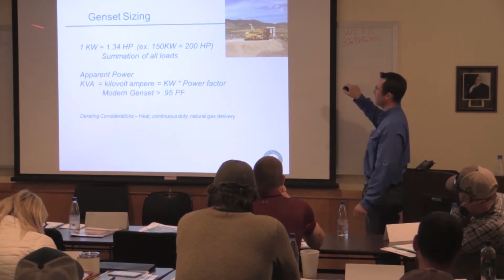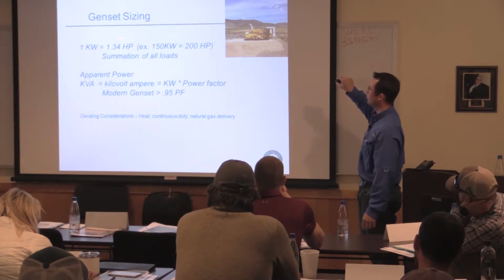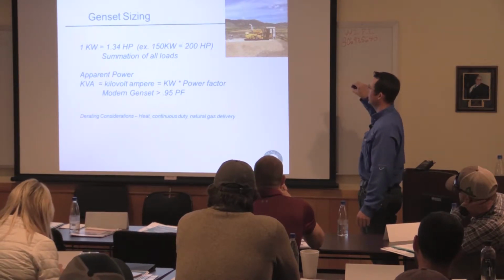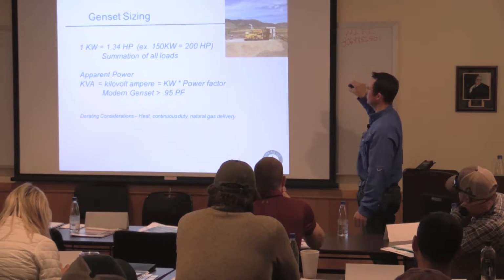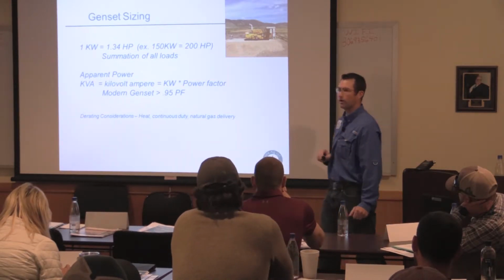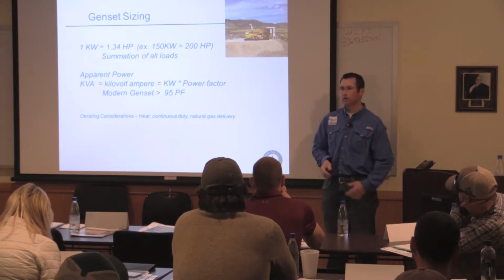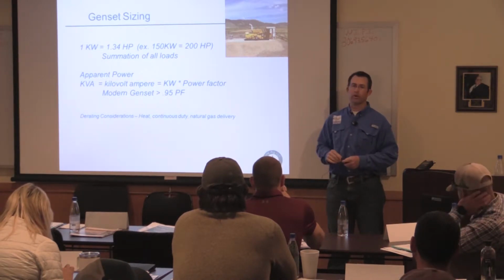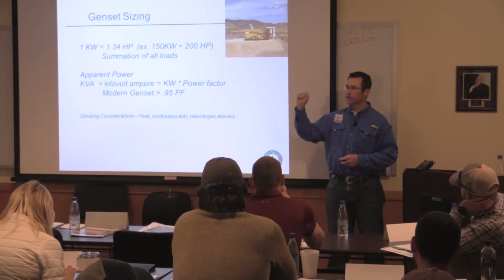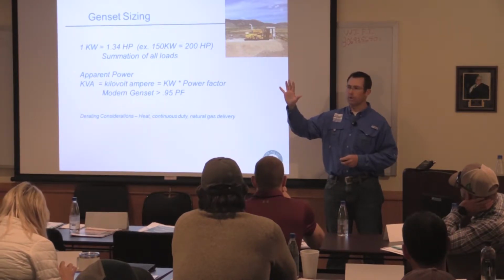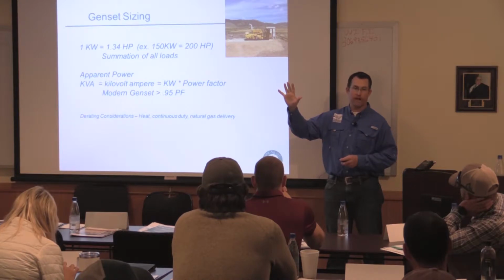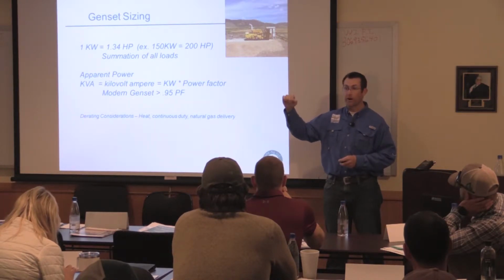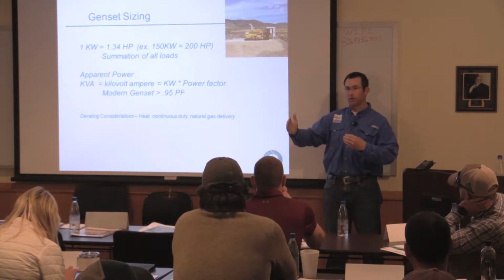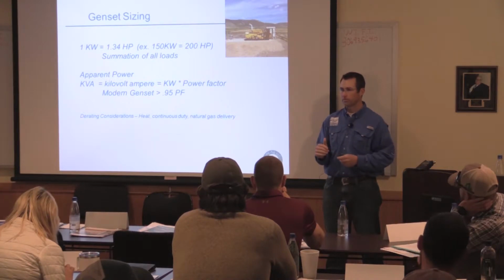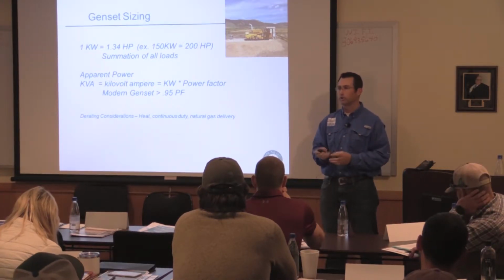The basic number that we'll look at is that 1 kilowatt equals 1.34 horsepower. So for example, if you've got a 150 kilowatt generator, you basically could be in the range of 200 horsepower for what you can operate off that. So keep it in mind, if you've got a couple of 40 horse subs, you do the math pretty quickly. If you're going to look at 5 40 horse subs on this, then you have to get really cautious about the math, because what's my line sizing look like? What's my wire down the hole look like? Am I really loading 40 horses, or am I loading 42 horses, or am I down to 33 horses on my sub? Okay, so that all comes into play when you're looking at generating this power.